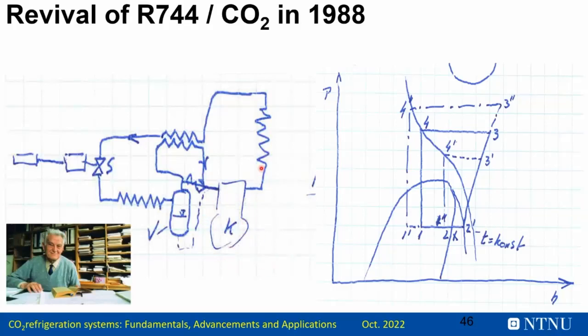like this, with the compressor, the gas cooler, an internal heat exchanger, a high pressure control valve, the evaporator, and then a low pressure receiver, helping so that the evaporator is always flooded, and the suction line heat exchanger makes the compressor safe and superheats the vapor to the compressor. And the innovation at that time was to utilize a high pressure control valve instead of a normal expansion device controlling the superheat. The pressure valve controls the high side pressure actively to achieve the optimum high side pressure, to make the best COP of the system depending on the condition.